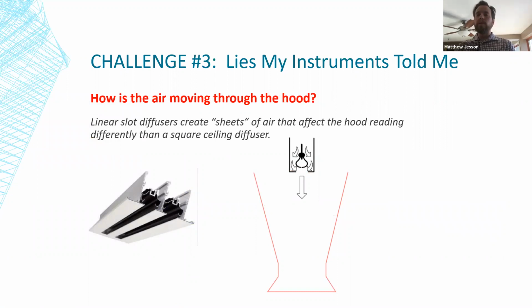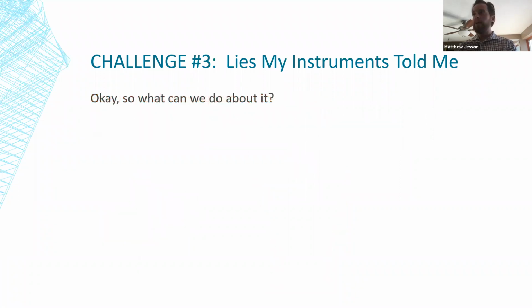On linear slot diffusers, it can read pretty differently than it does on a square ceiling diffuser that's spreading the airflow out. If it's coming straight down or directing it to the side, it can create a sheet of air that sticks to the hood side, and it can read that really differently. Or it can blast right down through, similar to the outlets we were just talking about. I've also experimented on slot diffusers, if you're using the square hood on a 2-foot wide slot diffuser, if you put it smack dab in the middle versus on the edge of the hood, you can get two very different readings. Okay, so what can we do about it? Sometimes your hood is going to lie to you. So what do you do about it?